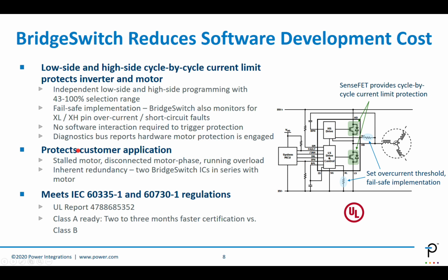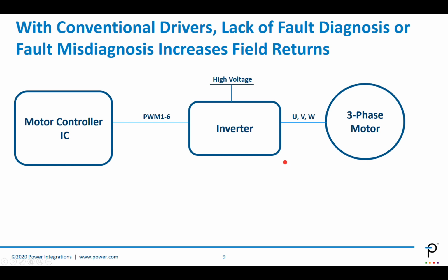Another use case is fault conditions which the customer needs to protect their application against. For example, a stalled motor, a disconnected motor phase, or running overload. All of these are possible to enable with BridgeSwitch without software intervention. A study showed that 30% of HVAC and fridge compressor repairs are no fault found. This is due to lack of diagnostics or misdiagnostics and generates unnecessary costs throughout the supply chain. Current motor driver IC solutions don't have the capability to specifically monitor and report what is wrong and where.